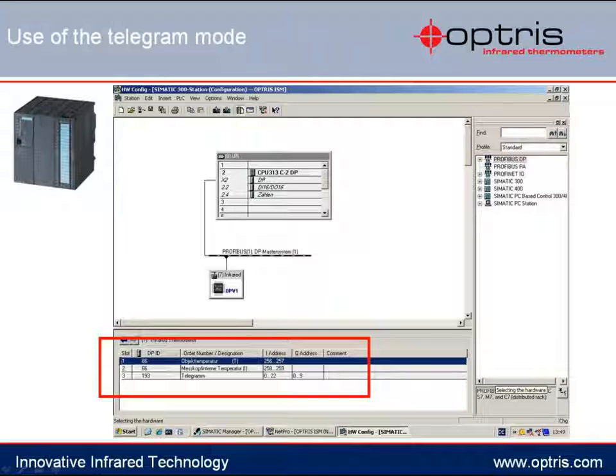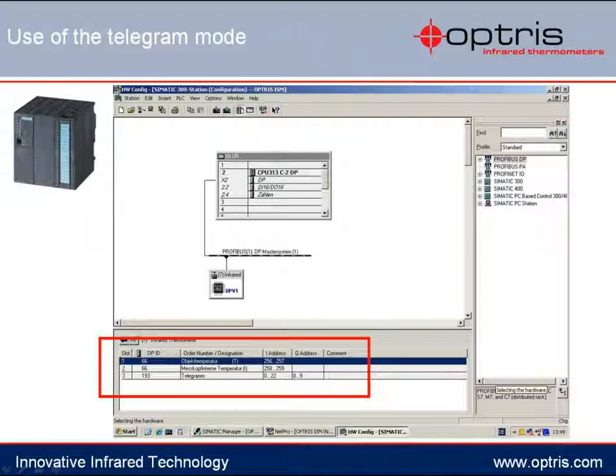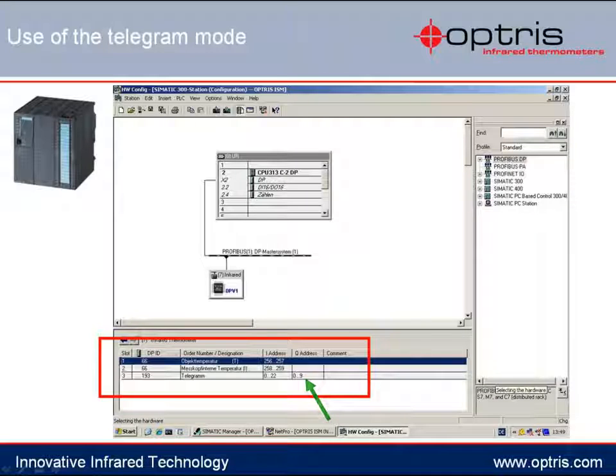Additional orders can include, for example, changing the emissivity at a temperature sensor or setting up an alarm. In the next examples, I will show you the appropriate approach for sending and receiving a telegram. The principle is always the same: 10 bytes will be sent to the temperature sensor, and the PLC will receive a reply from the sensor with the corresponding 23 answer bytes.